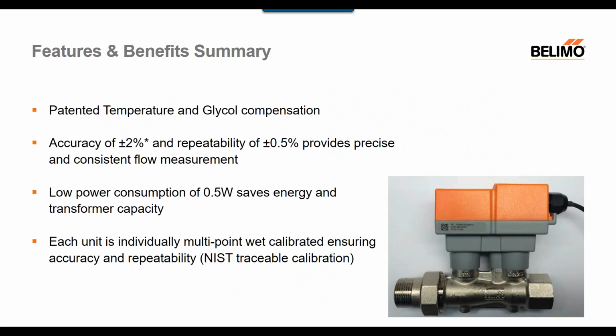Finally, let's recap on some of the features and benefits. We have patented temperature and glycol compensation, accuracy of plus or minus 2%, and repeatability of 0.5%, which provides precise and consistent flow measurements. We also have low power consumption of 0.5 watt, which saves energy and transformer capacity. Each unit is individually multi-point wet calibrated, ensuring accuracy and repeatability, and all NIST traceable.